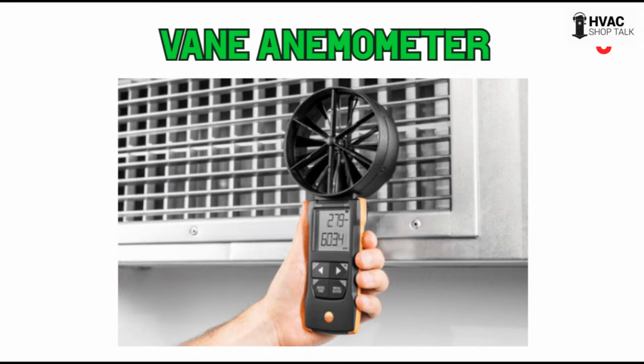The vane anemometer basically looks like a fan. They can be really small, like 2 inches across, or larger, like this Testo one—I think it's the Testo 417. If anyone in the chat knows for sure, feel free to tell me. It's a really nice one, gets a good cross section of air to measure. Air either blows across it or draws through it—on a return, I think of it as drawing through it. You measure how fast the air is moving through it, then make a calculation based on the size of the grill you're on to get a CFM measurement.